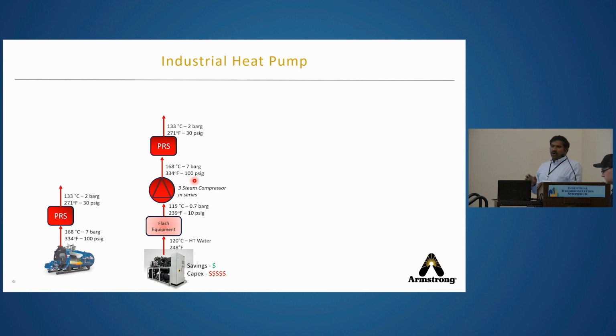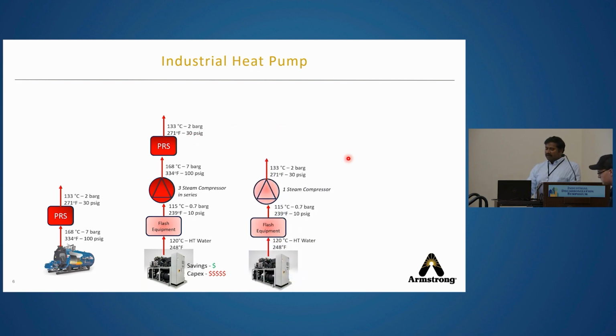So far, they kept their process information just like a black box. And when we asked what is their actual pressure they need, they say 30 PSI of steam in their process application. Then we gave a heat pump design where we have a heat pump with only one steam compressor, MVR, in series, to get it up to 30 PSI. Even in this case, the operating cost is not that lucrative, the CapEx is more, and the savings is a bit better than the previous design.